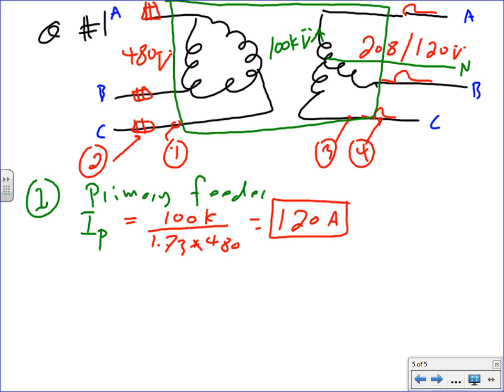A healthy 120 amp. Okay? Now here's the moment of truth, guys. My code uses 1.25 to size a conductor based on continuous load. Other people don't. So let's just use 1.25, but you don't have to use 1.25. When we go to the commercial, I'll start telling you guys.